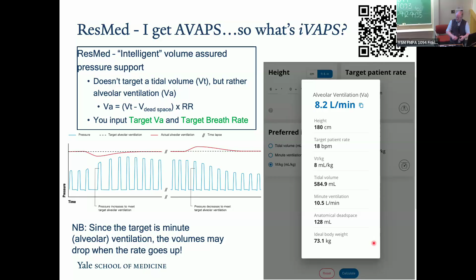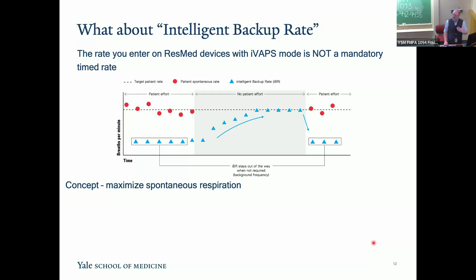So what is this intelligent backup rate? The rate that you enter on ResMed devices, which are in iVAPS mode, is not a mandatory backup rate. So when you say target rate 18, that's not the vent kicking in at 18 as long as your spontaneous rate is less than 18. It's not what's happening. So this is their diagram of the intelligent backup rate. And what's happening is they're trying to maximize spontaneous ventilation in these patients in order to encourage synchrony and patient effort. So you enter a target rate, and I told you, my number of 18. So that's what you're hoping the patient's spontaneous rate is.